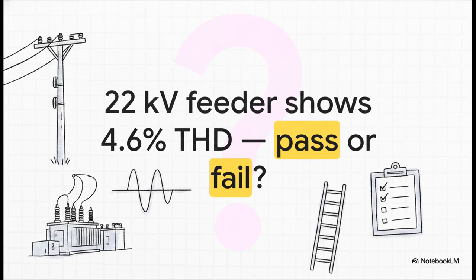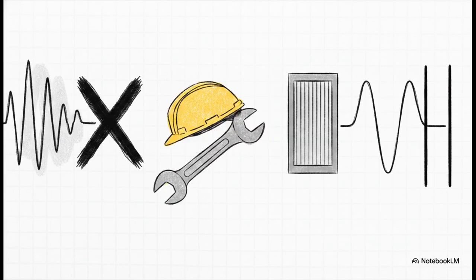Imagine you're auditing a 22 kilovolt feeder connection for a brand new facility. You take a reading at the point of common coupling, and your meter shows 4.6% THD. Based on that regulatory ladder we just talked about, is this connection compliant? Think about those tiers for a second. No way. That is a hard fail. Because you're in the medium voltage 22 kilovolt tier, the THD limit is exactly 4.0%. So a reading of 4.6% isn't just a minor drift, it's an outright regulatory violation.